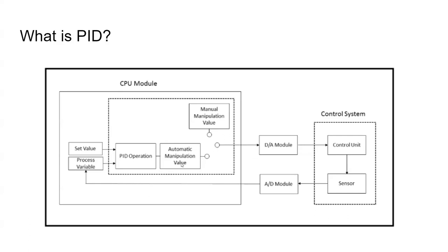Where does that manipulation value go? It goes to an analog card — a DA module, which means it's turning a digital binary value, like 16,000, into an analog response such as 10 volts, 5 volts, or 20 milliamps. That value is sent to the control system, which interprets it and operates accordingly. Maybe we generate 7.5 volts, and then the VFD or whatever control system interprets that output and generates its appropriate response.